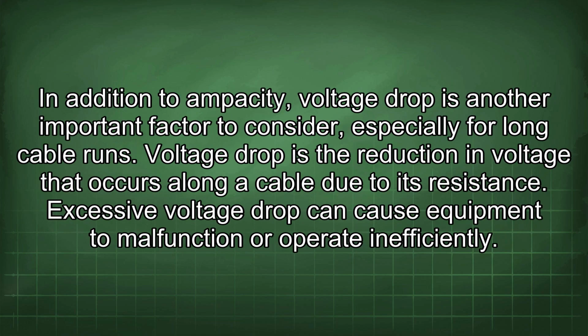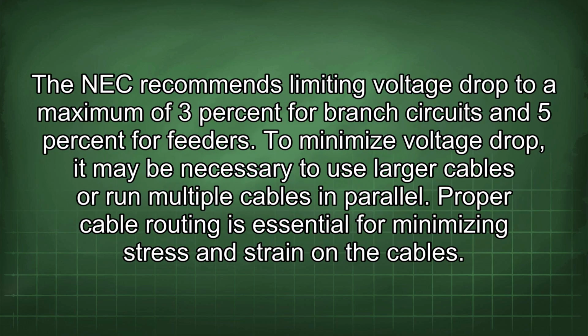In addition to ampacity, voltage drop is another important factor to consider, especially for long cable runs. Voltage drop is the reduction in voltage that occurs along a cable due to its resistance. Excessive voltage drop can cause equipment to malfunction or operate inefficiently. The NEC recommends limiting voltage drop to a maximum of 3% for branch circuits and 5% for feeders. To minimize voltage drop, it may be necessary to use larger cables or run multiple cables in parallel.